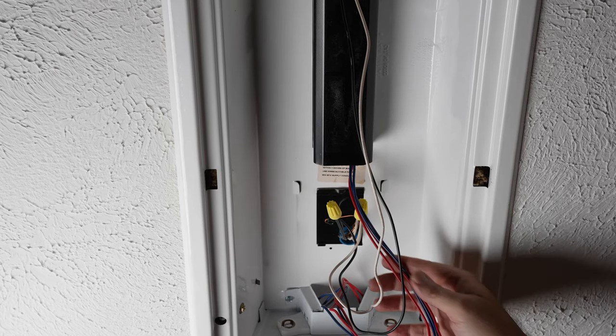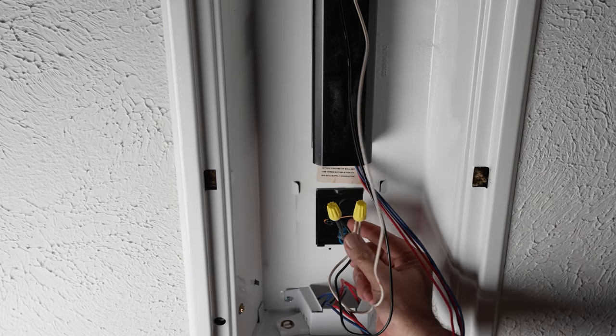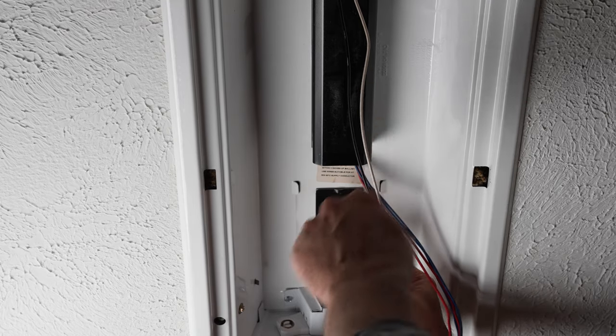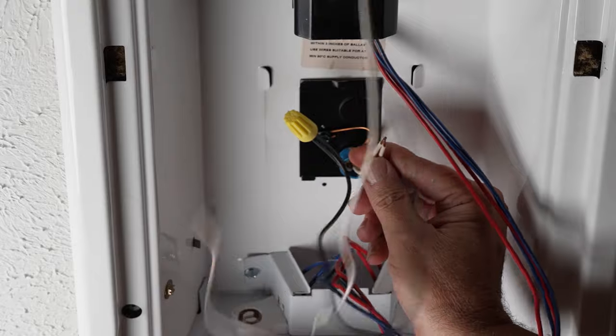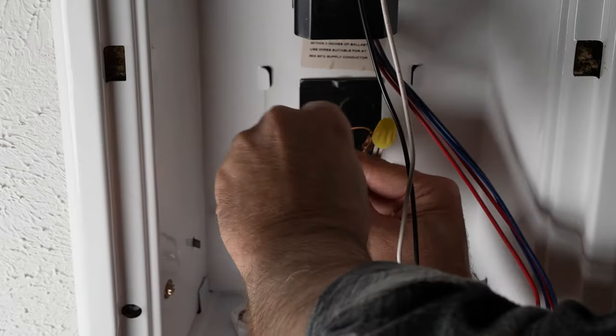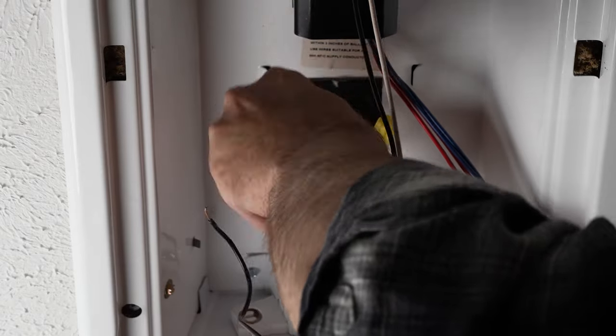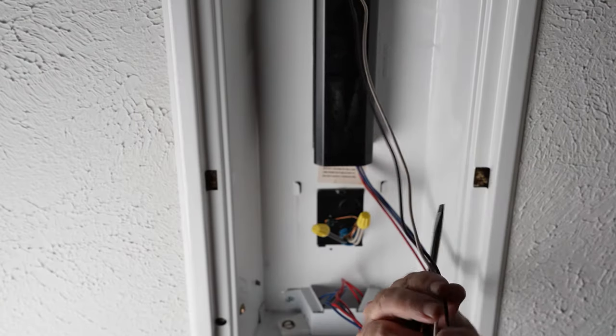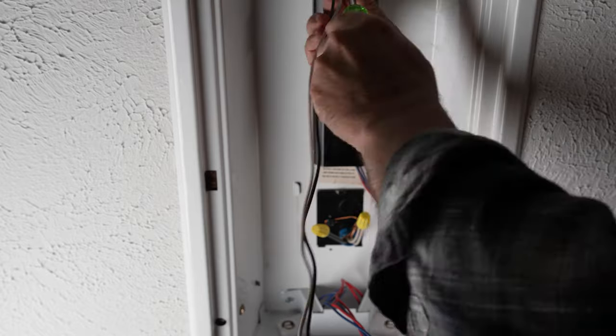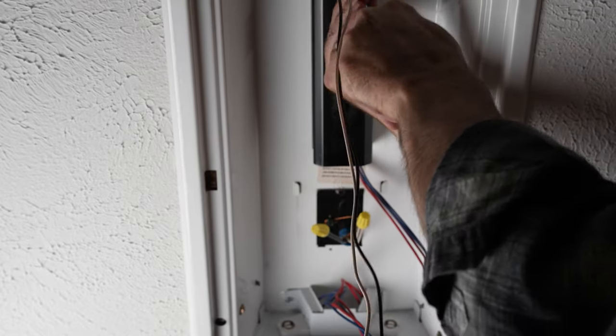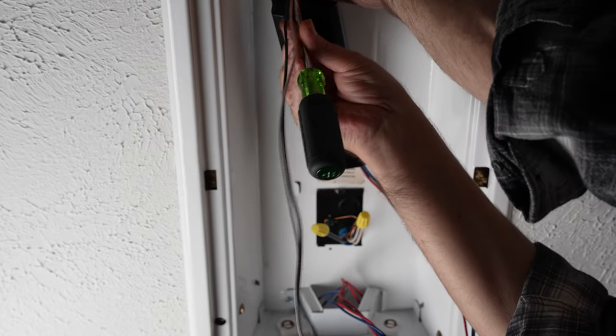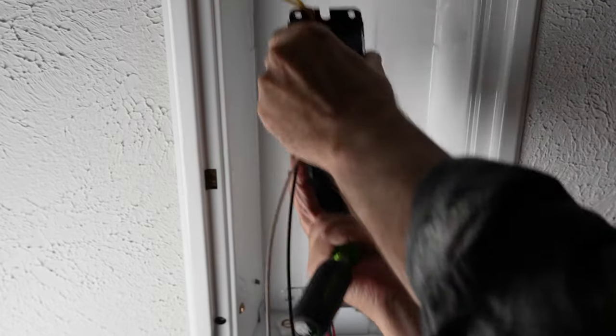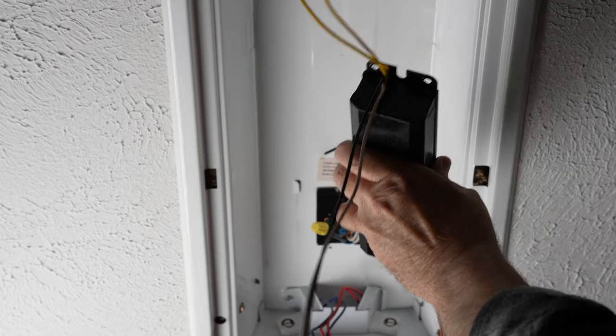First thing we're going to do is get the breaker turned off. Now we're going to disconnect the hot and the neutral from the ballast. Now time to get the ballast out of here once we have it disconnected from the power. So it has a screw in one end of it and then it slides into a piece of metal on the other side. So we're going to take that screw out and slide the ballast right out of the fixture.